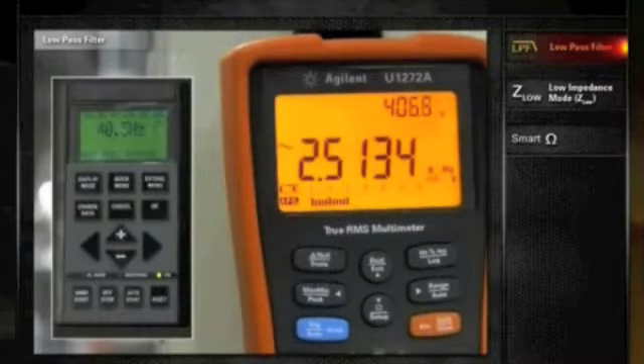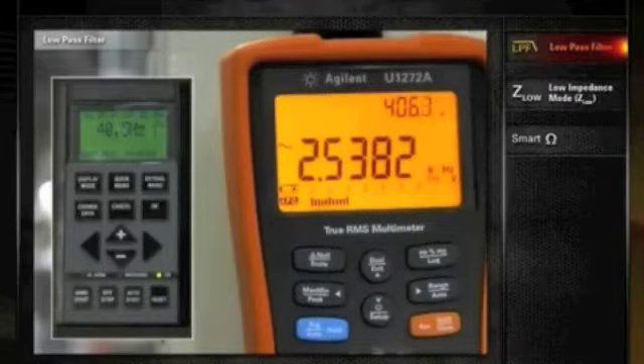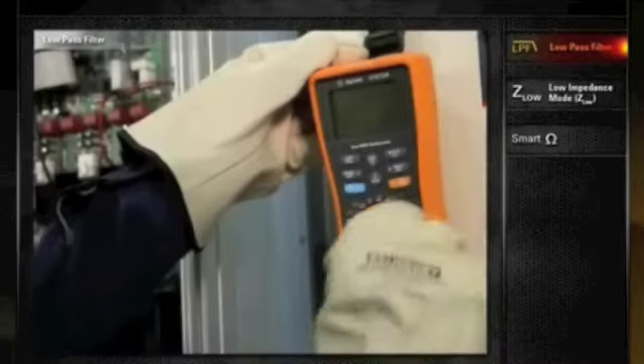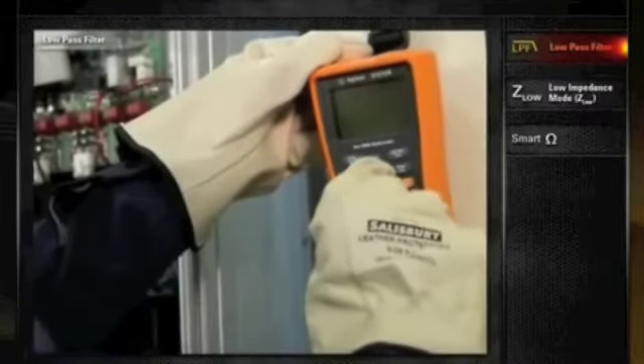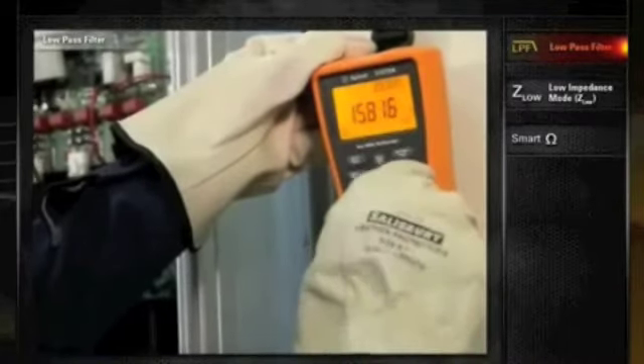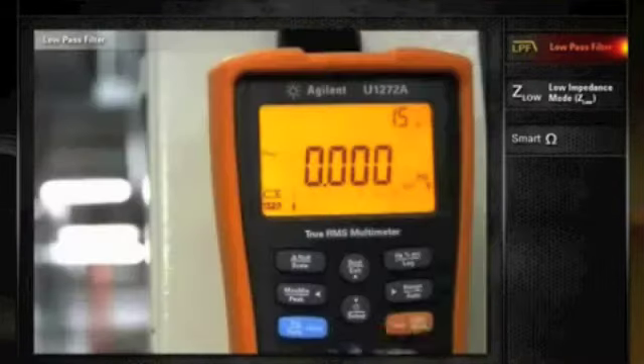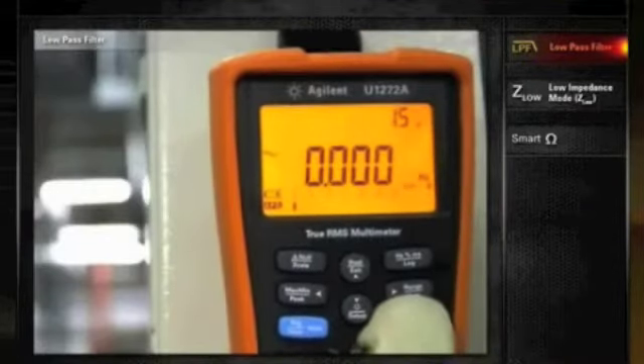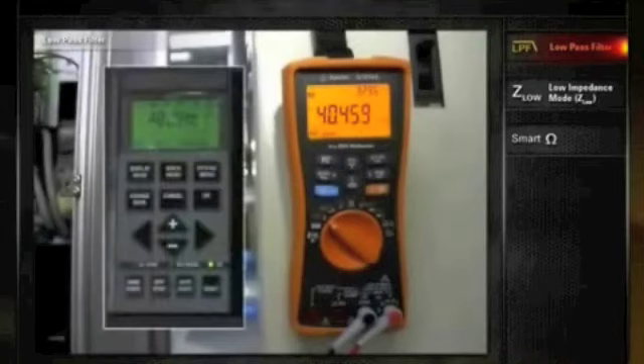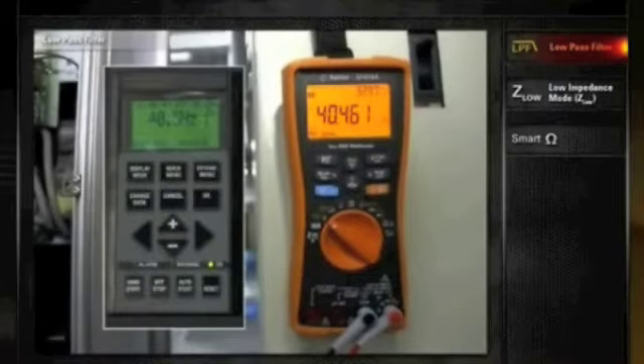This difference could be due to unwanted high-frequency components generated by the VFD. The U1270 series handheld offers a 1 kHz low-pass filter to eliminate unwanted high-frequency components, allowing technicians to accurately measure VFD output.